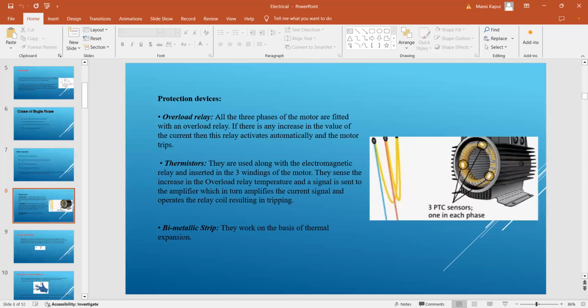Second one is the thermistor. They are used along with the electromagnetic relay, inserted in the winding. Can you see in this figure? They are inserted inside the winding. Yes, sir. They sense the increase in temperature. So what are they sensing? They are sensing the temperature in the winding. And when the temperature is high, a signal is sent to the amplifier, and we turn this temperature into a current signal, and it is going to operate this coil, and it is going to trip your motor.